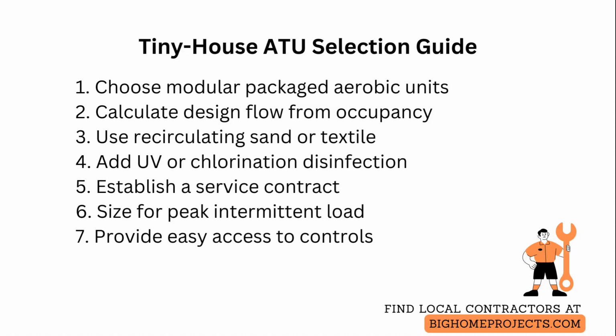For owners planning any type of gray water reuse or tight discharge limits, add ultraviolet disinfection or a controlled chlorination contact chamber after the final filter to reliably reduce pathogen levels. Ultraviolet is low maintenance but requires stable power, while chlorination requires careful residual monitoring.